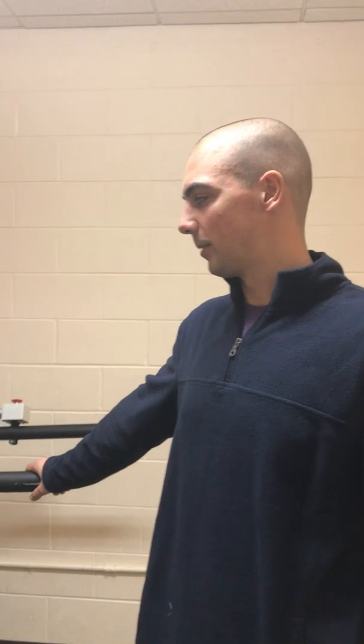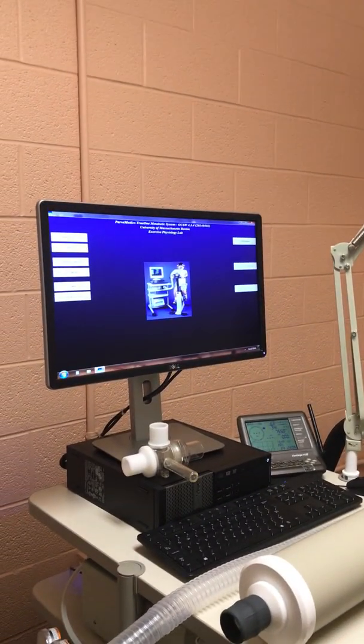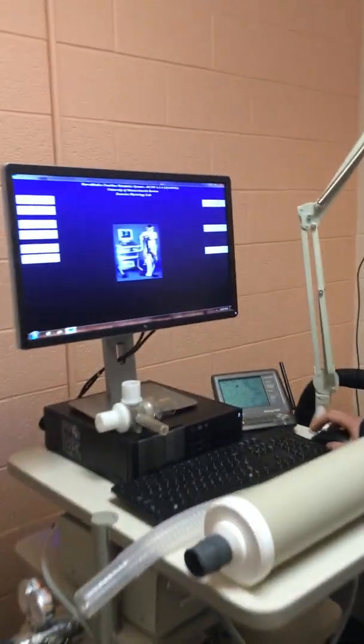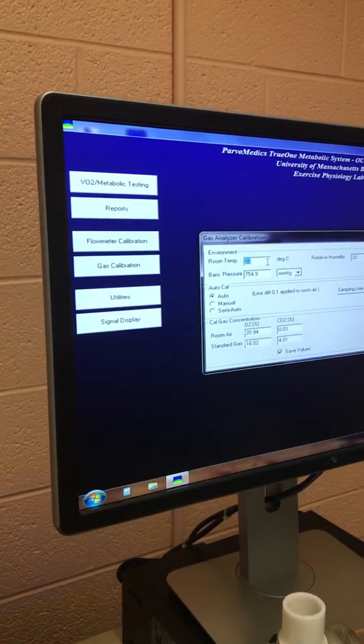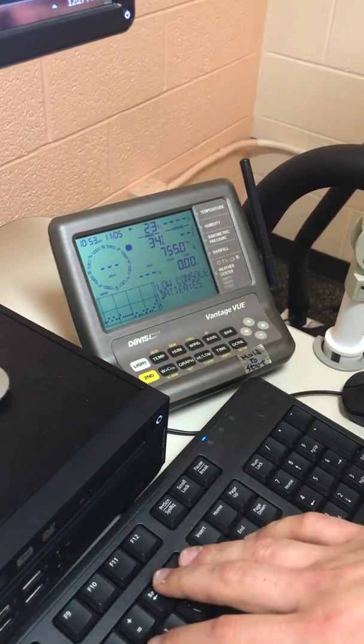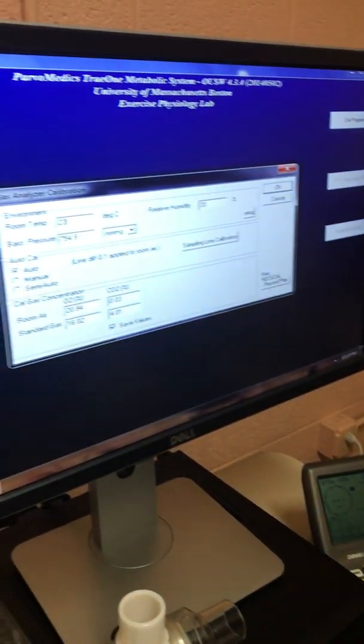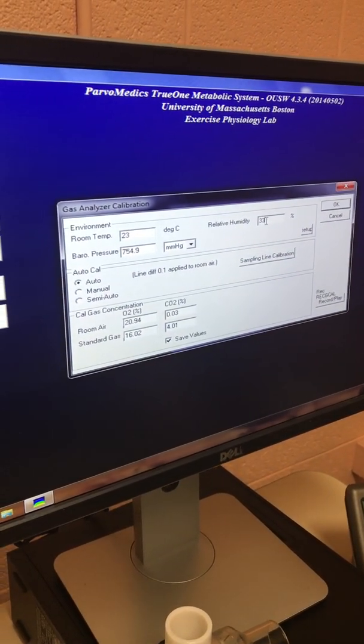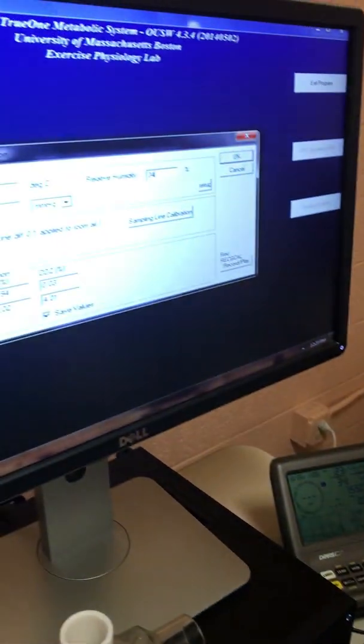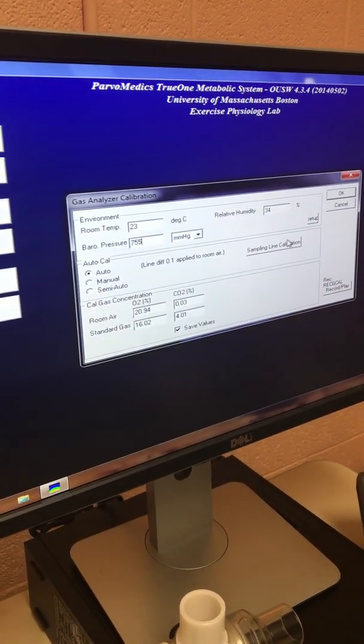So here we're going to do a flow meter and gas calibration for indirect calorimetry if we were going to set up a maximum VO2 test. So we're going to go over to our Parvomedics software here. We're going to hit gas calibration. And the first thing that we need to do is look at our environmental conditions. So we're going to look at room temperature, and inside it says 23 degrees. So we're going to insert that into the software. We're going to look at relative humidity, and it looks like we're at 34%, so 34% humidity, and the barometric pressure is 755, so it's increased slightly. And then we're going to hit OK.